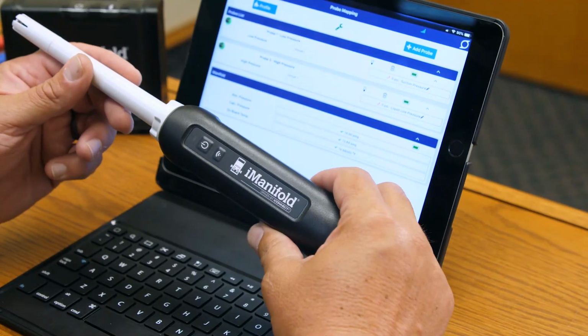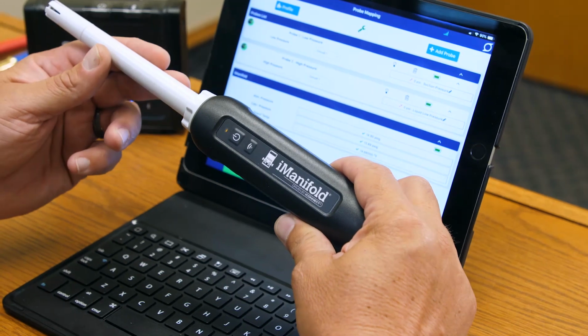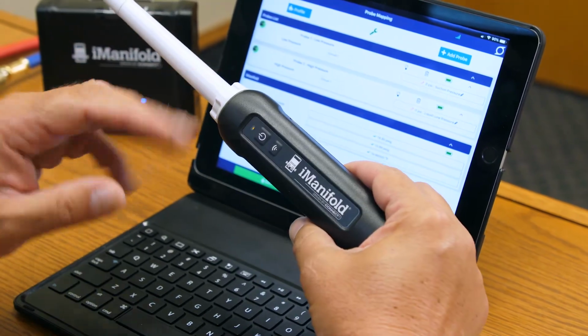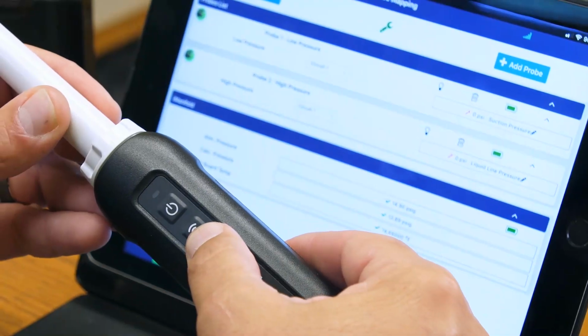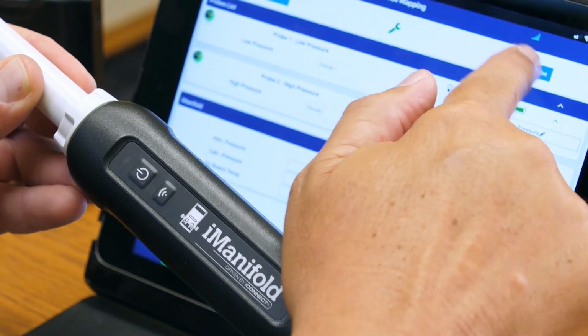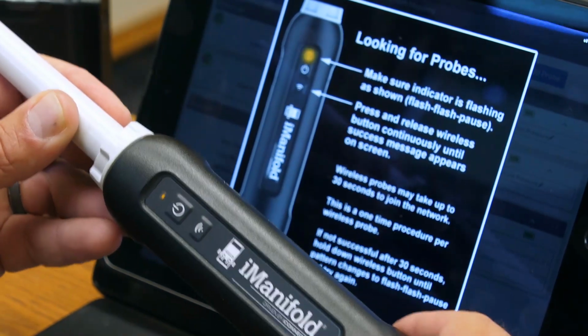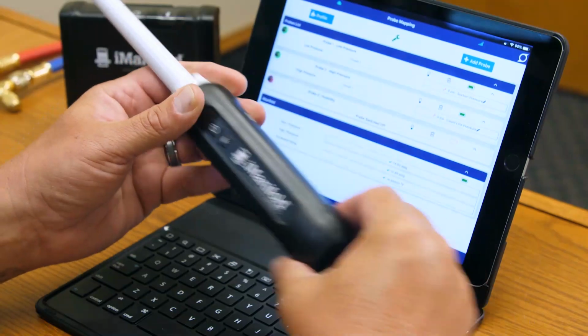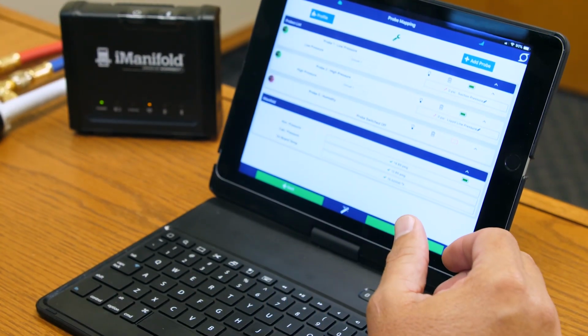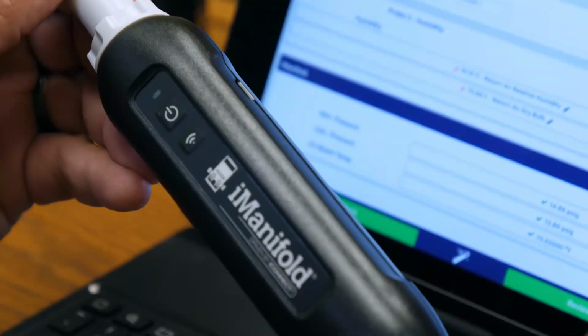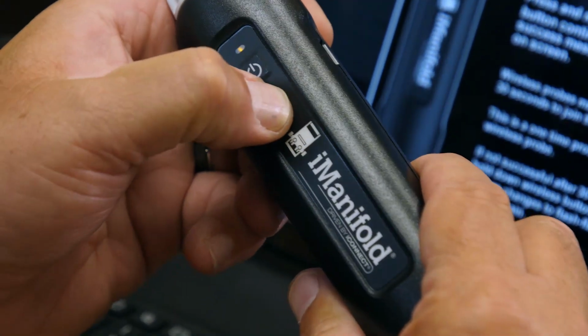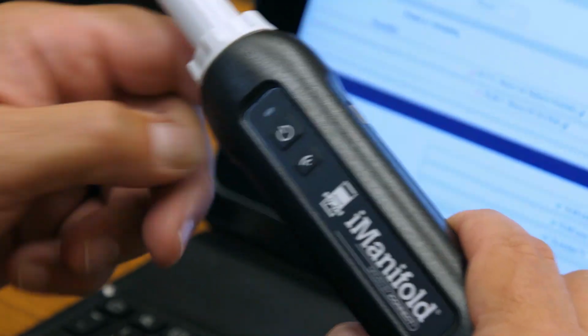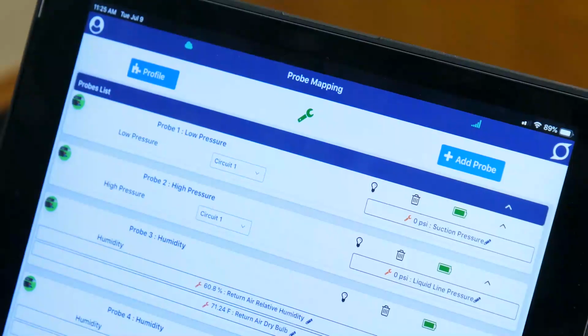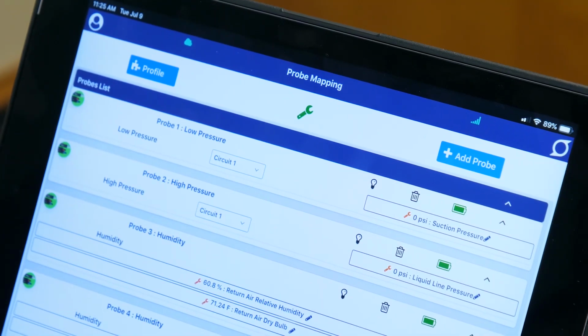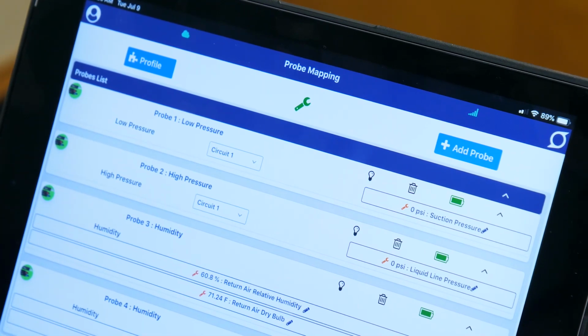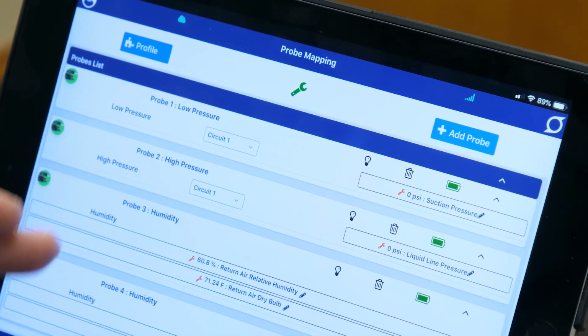Now for our temperature humidity hygrometers, our 911Ms, we're going to do the same thing for both. Everything's flashing the way it should: add probe, press our wireless key, that probe is added. Add probe, wireless key again, probe added. Now that all of our probes are present, we have our low pressure, our high pressure, and 2 humidity temperature probes.